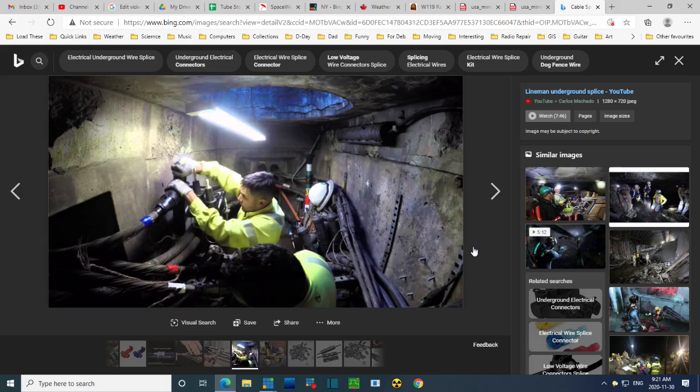Ooh, look at these guys. Now, this is an older manhole. You see, the roof is beginning to fail right in here. This is a communications splice. These are not very watertight. See how it's mounted up high on the wall? It has a little bicycle thing here. You might be able to pressurize these. Some of these are run with nitrogen in them. The idea is if you get a hole, the nitrogen comes out, the water does not go in. You see the drop in pressure. You can then go out and measure. Maybe that's what this is. You measure the pressure here and you can deduce where the leak is on these communications cables.